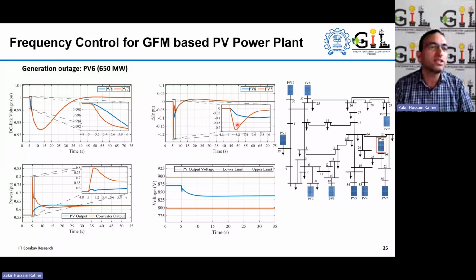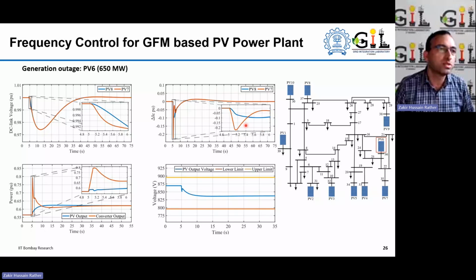Or you can see here it is providing more response here, the current response from the DC link compared to the power plant 8, which is farther from the disturbance. So indicating that the lower the electrical distance of this power plant with respect to the disturbance location, it is actually providing relatively more response here. That is also reflected in terms of the voltage here and the power output.